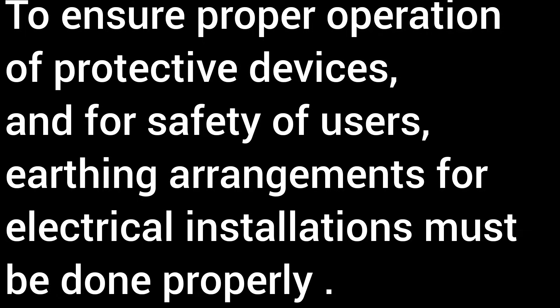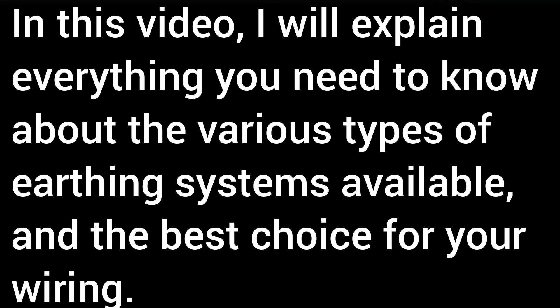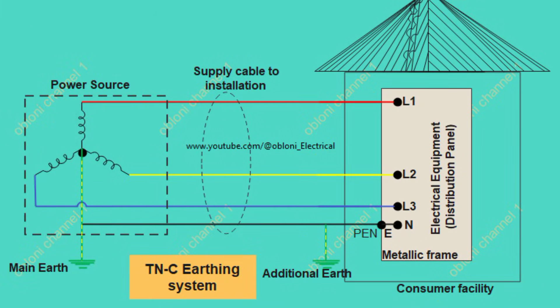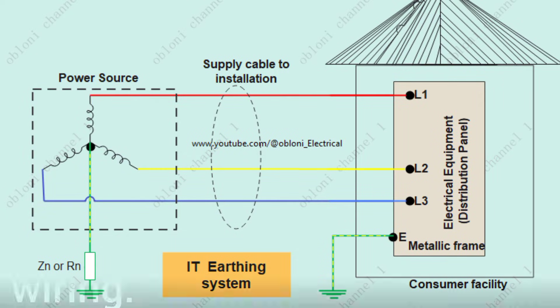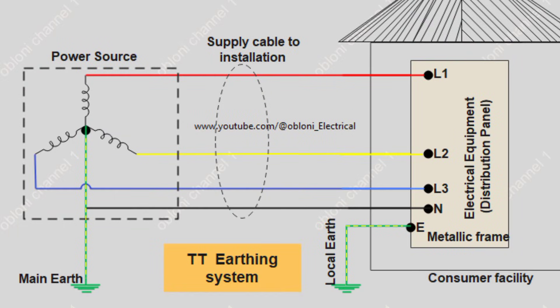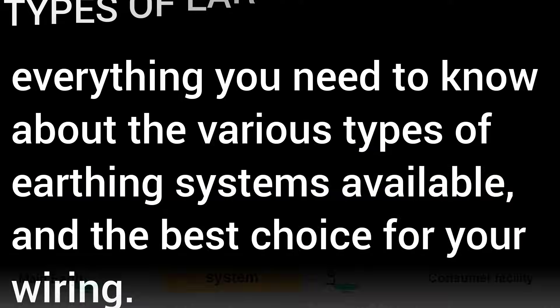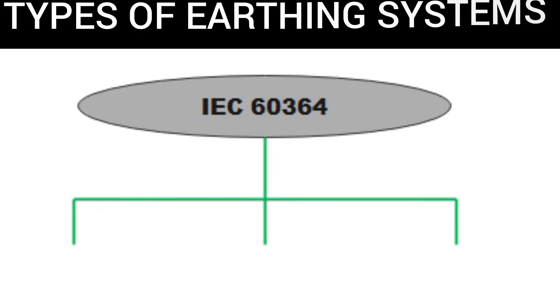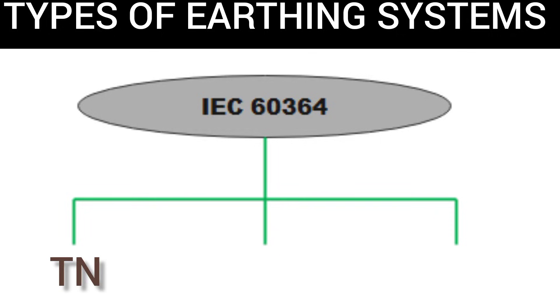In this video, I will explain everything you need to know about the various types of earthing systems available and the best choice for your wiring. The IEC 60364 distinguishes three major types of earthing systems using the two-letter codes TN, TT, and IT.